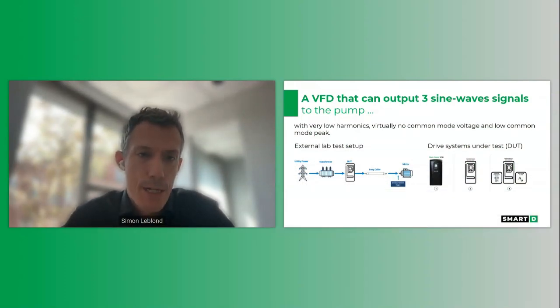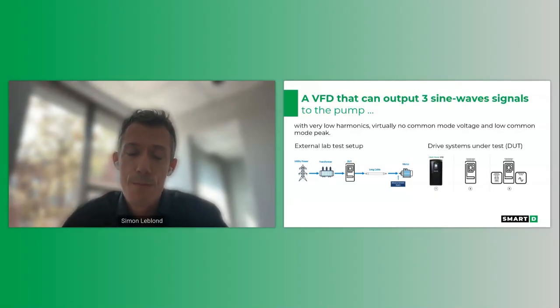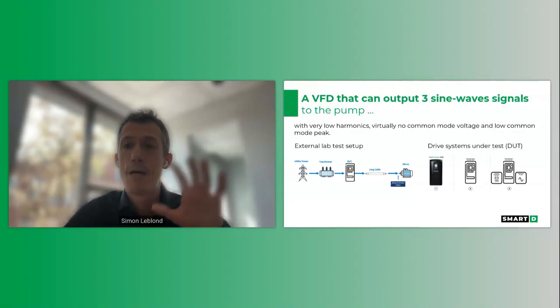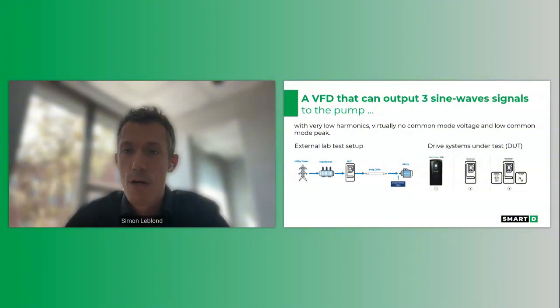We've been through external testing with a third-party lab to test our Clean Power VFD and see how it can output three sine wave signals directly to the pump, with very low harmonics, virtually no common mode voltage, and low common mode peak. The external lab setup has a transformer that gives a very stiff grid. It has a drive system under test with about 500 feet of cable, so we do have long cables in there, and then we have the motor. In terms of drive system under test, we have tested the Clean Power VFD, a conventional 6-pulse VFD, as well as a conventional 6-pulse VFD with both a passive harmonic filter and a sine wave filter on the motor side.